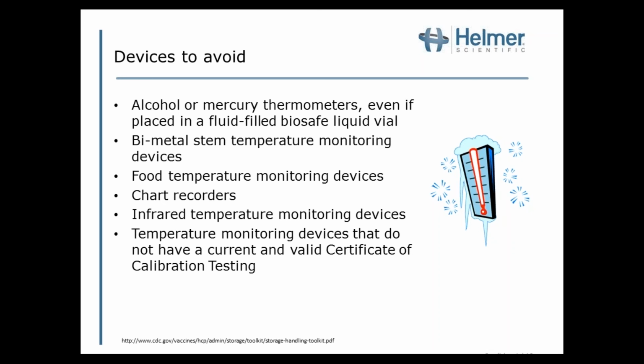And finally, the temperature monitoring devices do need to have a current and valid certificate of calibration, so that's just testing it against the lab and saying that the thermometer is indeed accurate, and it also is precise within plus or minus 1 degree Fahrenheit. Another thing you'll see sometimes with thermometers that's a requirement, and you'll probably see it on your certificate of calibration, is also called a certificate of traceability. And what that does is it actually allows you to trace the calibration of the thermometer all the way back to the National Institute of Standards and Technology. So that organization calibrates thermometers for labs, which will calibrate your thermometer, and that's where the traceability comes from.